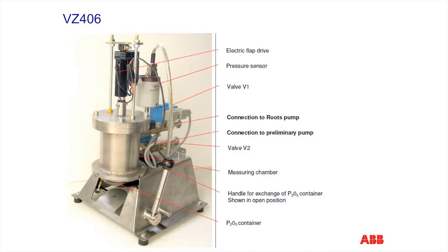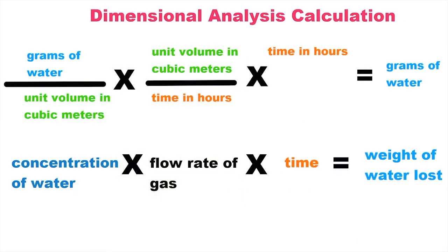Knowing these values allows one to calculate the total weight of water removed from the transformer. Using simple dimensional analysis, you can see that the product of the concentration of water in grams per cubic meter times the pumping rate in cubic meters per hour times the number of hours yields the number of grams of water extracted from the system.